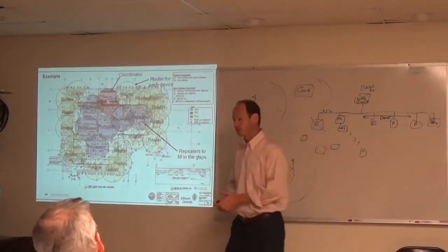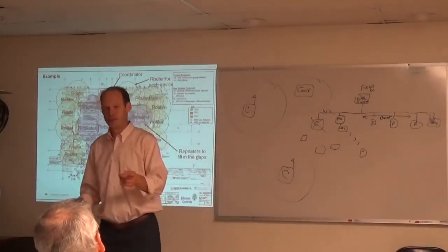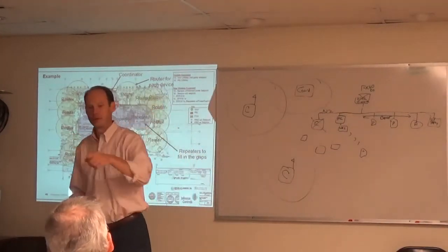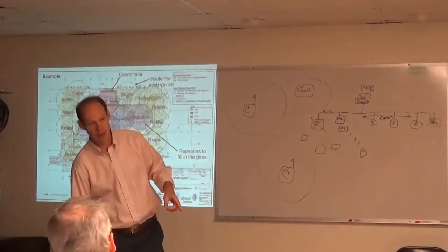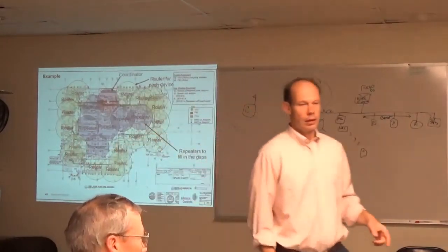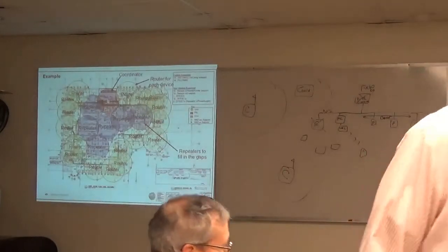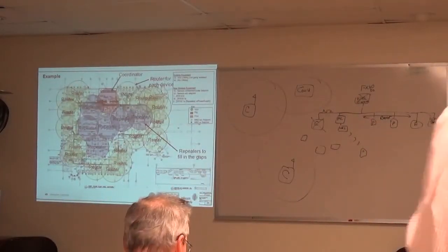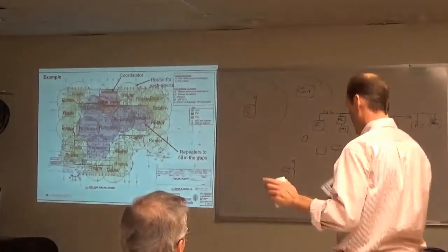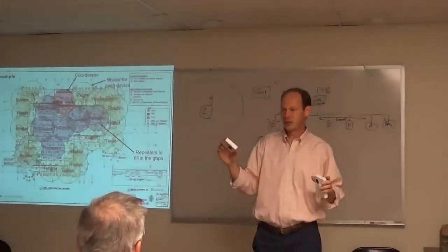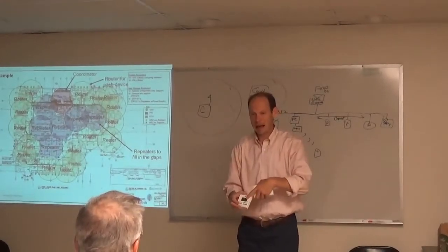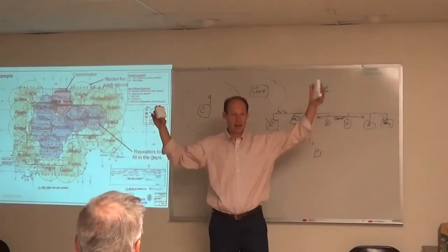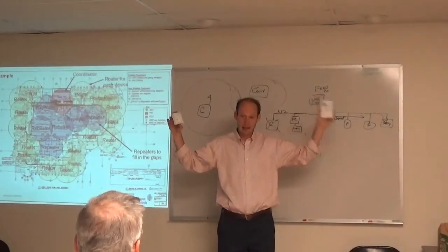And we do have a tool, and it looks like the WRZ7860 is, wherever that thing is. Yeah, we have one of those guys. Here, this guy. So you take a regular sensor, like this, and then it's called a wireless sensing tool. It's basically this with a little battery pack on the back. So you can take this thing and put it where you have one flag, you go to the spot where you have another flag, you hit the button on the side, press it.